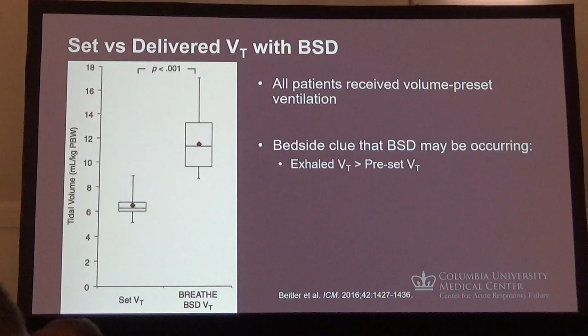Because my experience with most ventilators suggests that the ventilator is documenting the inspiratory cycle volume, and every time a new inspiratory cycle occurs, the ventilator resets that volume to 0. So it will never recognize the 400 plus 400 equals 800 on the inspiratory side. All it's reporting on that VTI, the tidal volume inspiratory, is the individual cycle volume. So we'll only call it 400.